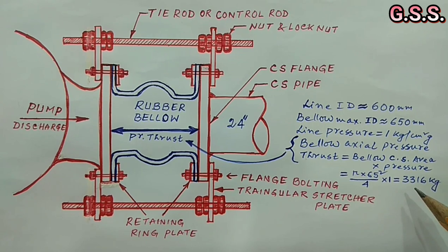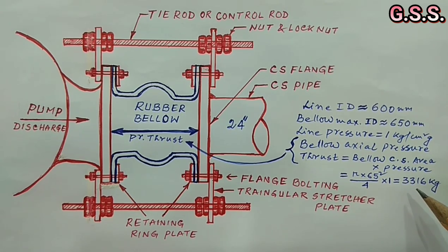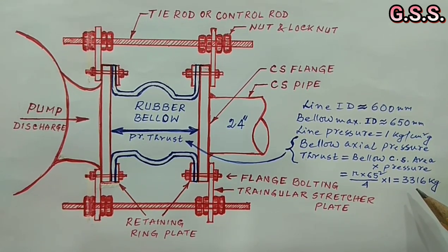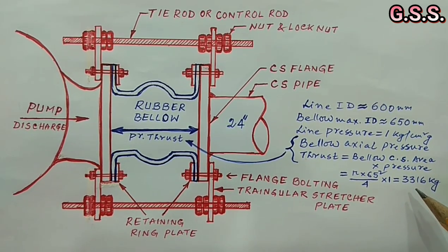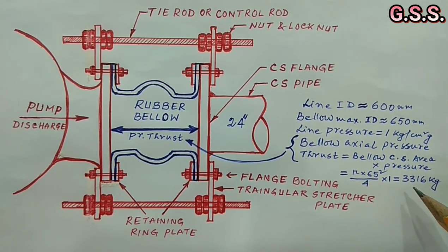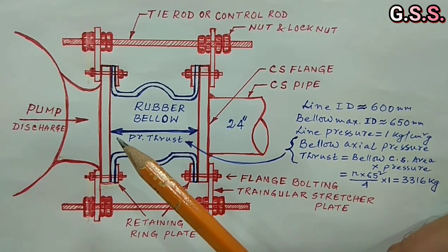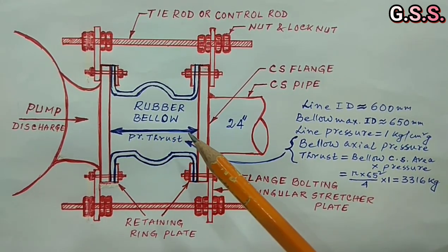If line pressure is 5 bar gauge that means 5 kg per cm square gauge then pressure thrust across the bellow will be 5 times that means it will be more than 15 ton. This axial pressure thrust acts axially along the bellow and due to this axial pressure thrust, bellow will try to expand axially.